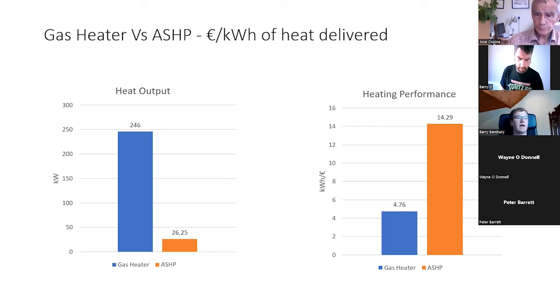So the whole aim here will be to minimize the use of the gas heater, or eliminate it completely if we can, because it's way cheaper to use the air source heat pump. But being mindful as well, if the air source heat pump is going to need more time to heat up the space, suddenly fabric heat loss becomes a bigger part of the picture, and that's where it becomes really interesting.